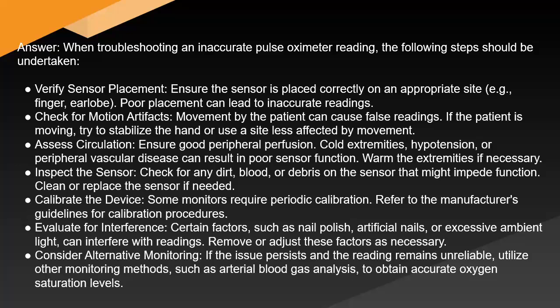Answer: when troubleshooting an inaccurate pulse oximeter reading, the following steps should be undertaken. Verify sensor placement. Ensure the sensor is placed correctly on an appropriate site, e.g. finger, earlobe. Poor placement can lead to inaccurate readings. Check for motion artifacts. Movement by the patient can cause false readings. If the patient is moving, try to stabilize the hand or use a site less affected by movement.